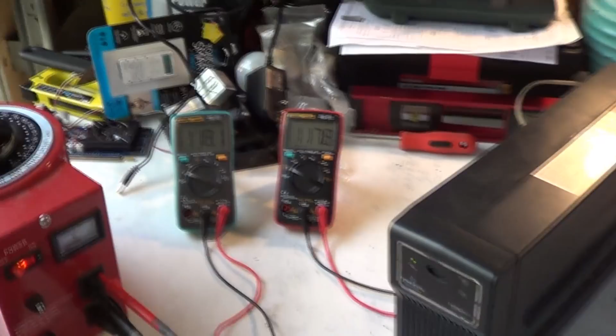I know it's a nerdy thing about which few people would ever care, but I always tell people when they ask me, buy the best uninterruptible power supply you can afford, and what's more, buy something with enough capacity that it's not always running right up against its limit. Because when it runs right up against its limit, it's beating the battery to death, it's beating the inverter to death. Time gets even with the batteries, and what ends up happening is a unit that could just barely make it long enough to save all your work and let you shut down the computer. In 3 years it only lasts half as long as it used to, and suddenly it's not long enough anymore.